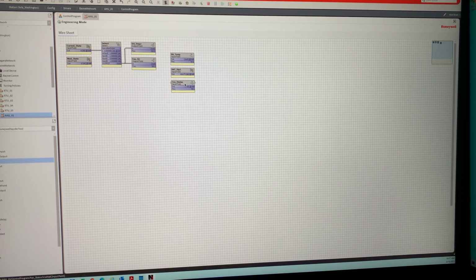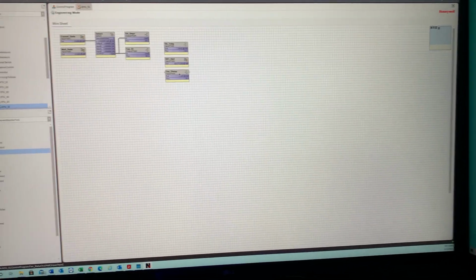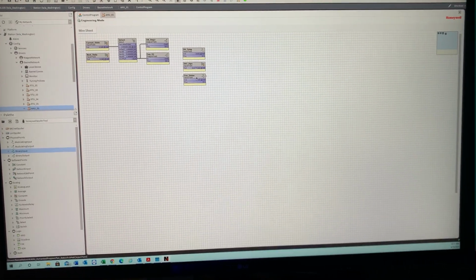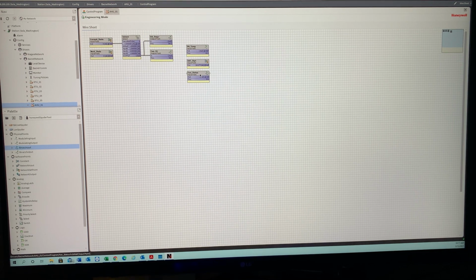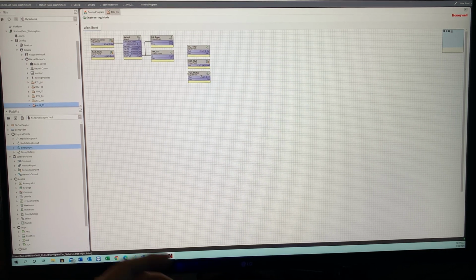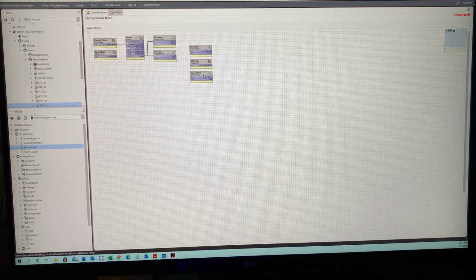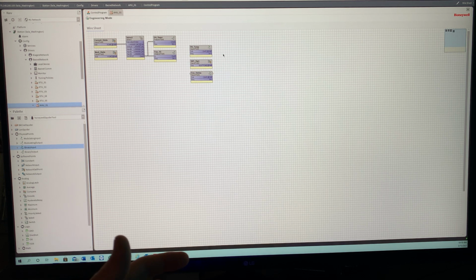But what I like to do is base it on fan status. Let's say, for instance, there's an issue and the communication between the controller and maybe a Jace goes down. What you could do is at least get the fan running, and then it'll start doing all its sequences based on looking at fan status. So we have our DAT set point and fan status.